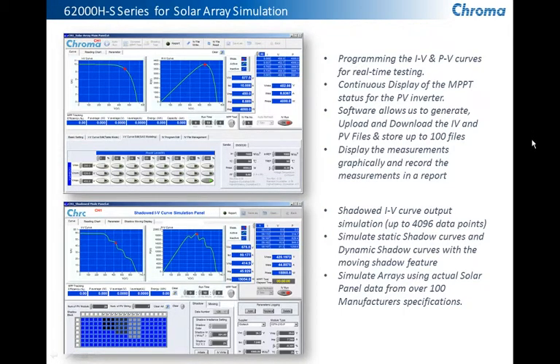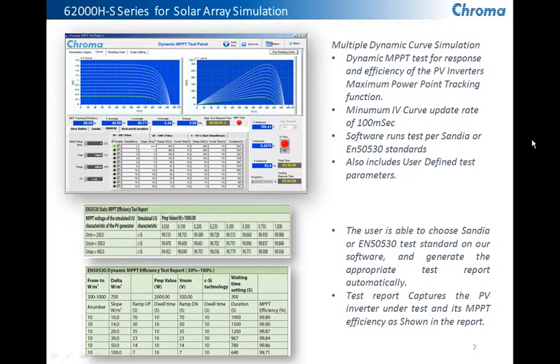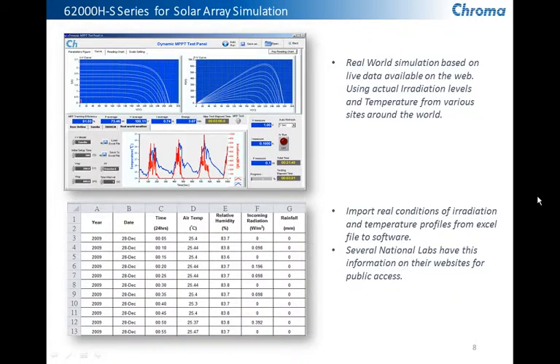We can also do what's called maximum power point dynamic testing and we can do that a couple of different ways. We can create multiple curves at different power levels and time those at different time intervals to input that. We can do this to actually test the response time of the PV inverters maximum power point tracking. We can also use real data of solar radiation levels and temperatures that can be downloaded from different sites mostly through some of our national labs out there. You can collect this kind of data and import that and load it into the software and create real-time real data with IV curves.